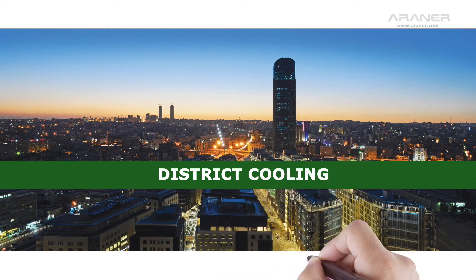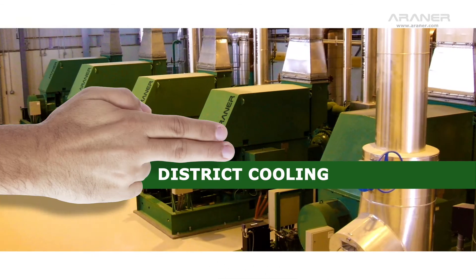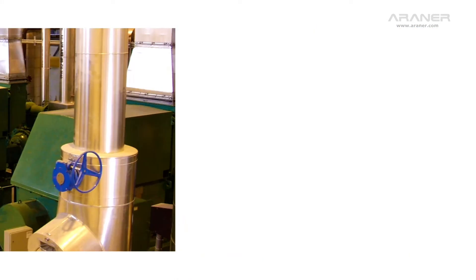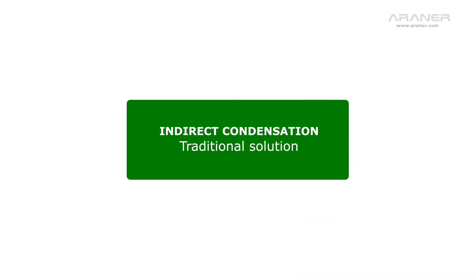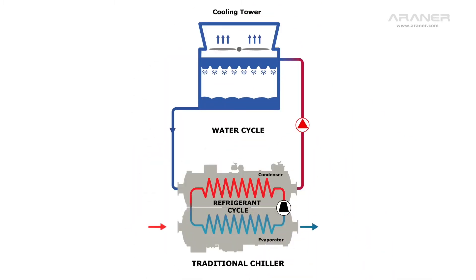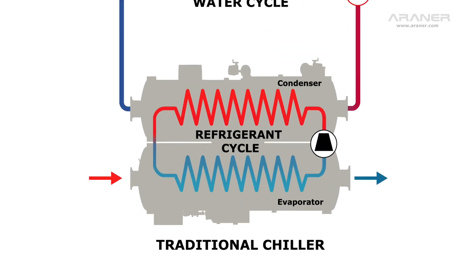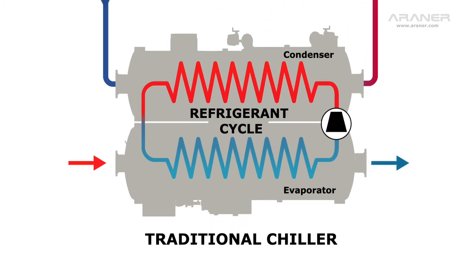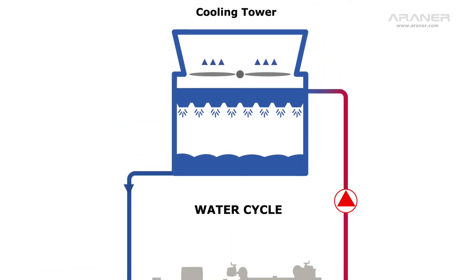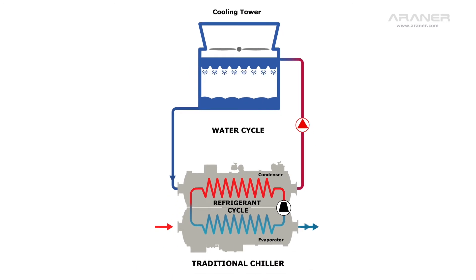In district cooling, during the refrigerant condensing process, the heat gained is rejected to the atmosphere. Traditionally, this process is done through indirect condensation in two stages. First, the refrigerant transfers the heat of condensation to a closed cooling water loop. Then, this water is cooled in a cooling tower and the heat is rejected into the atmosphere.